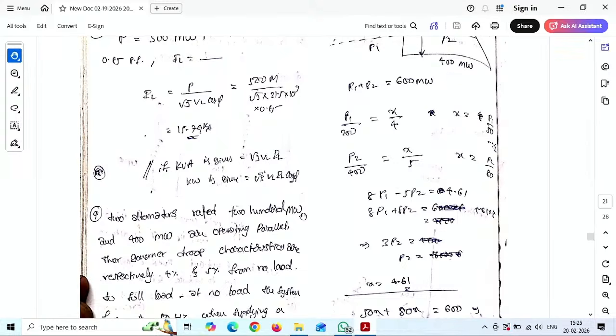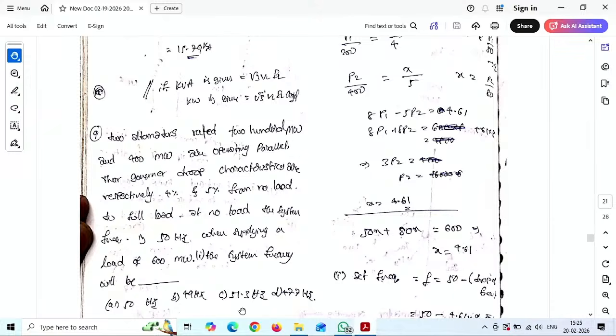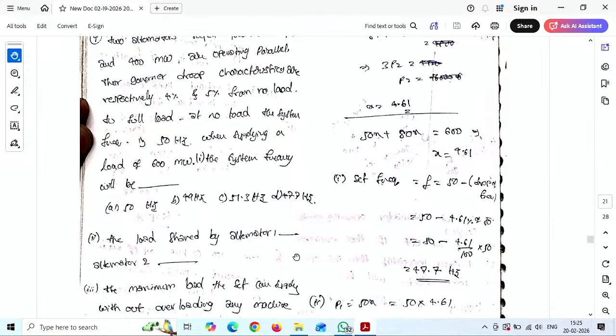Right, full load means now on this new load sharing, at this 600 load, P1 plus P2 load, at what frequency are they operating now? X percentage of 50 rated, correct, so 50 minus this X percentage of 50, that will result in 47 point some value, just for confirmation, 47 point. This is the set frequency. At this frequency, now if you calculate P1 and P2, we have maths here, equations, P1 and P2.